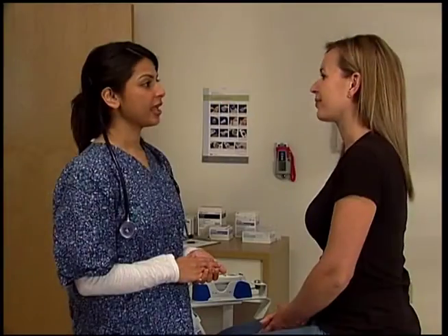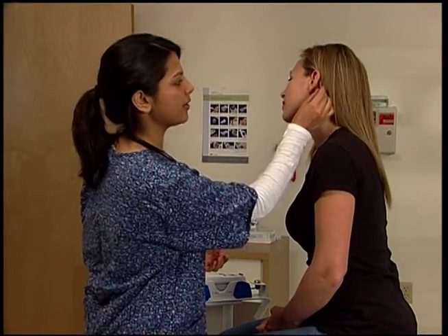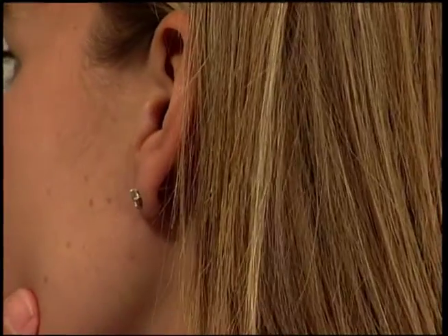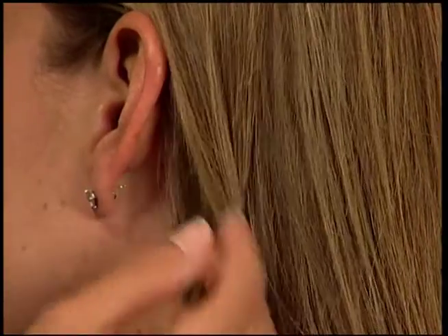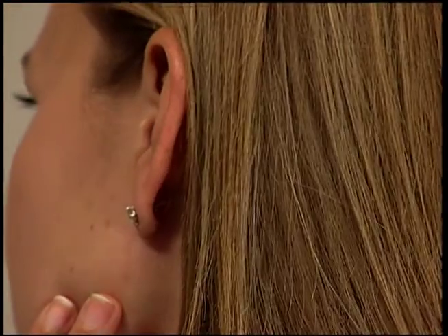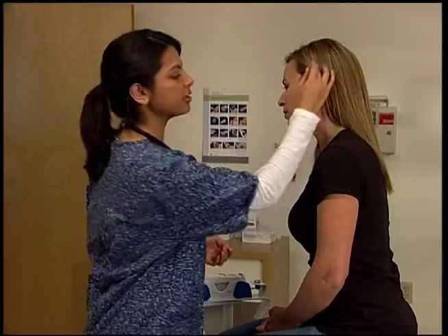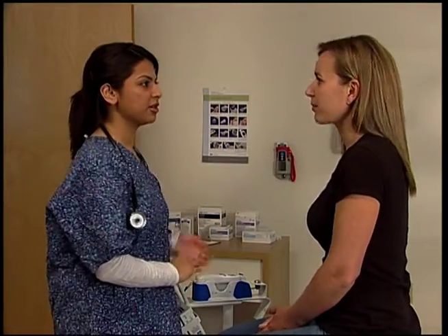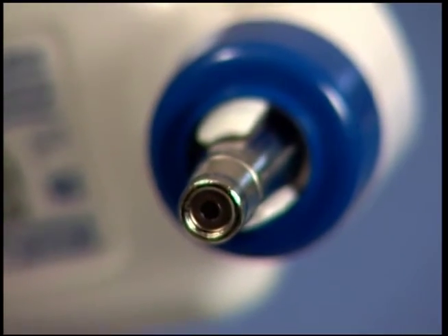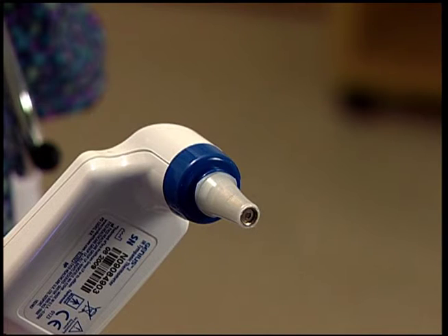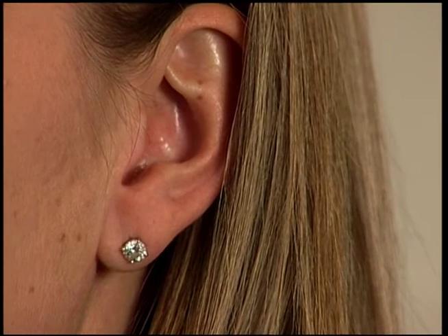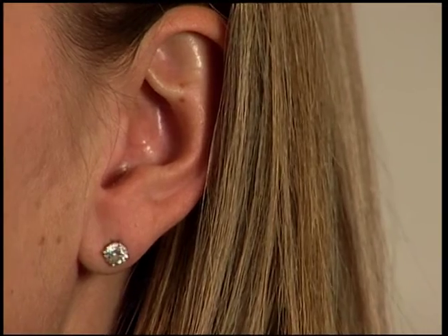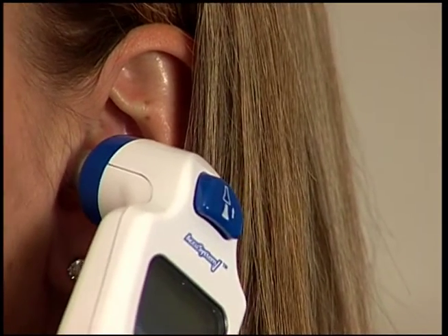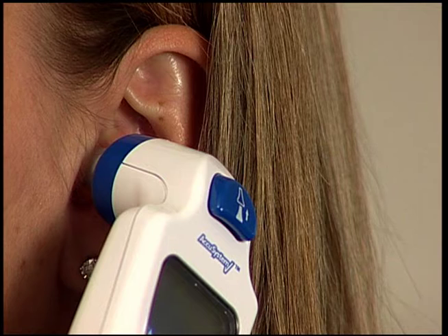To review, visually inspect each patient's ear before taking a temperature. Make sure the ear canal is dry and free of impacted earwax. Never use the probe in the presence of blood, water, or any other liquid in the ear canal. Visually inspect the probe lens to ensure that it is clean and free of cracks. Ensure the probe cover is fully seated, with no silver showing between the probe cover and the blue end cap on the thermometer. Make sure you get a comfortable seal around the probe tip and ear canal, positioning the tip with the angle of the ear canal to get the most accurate reading.